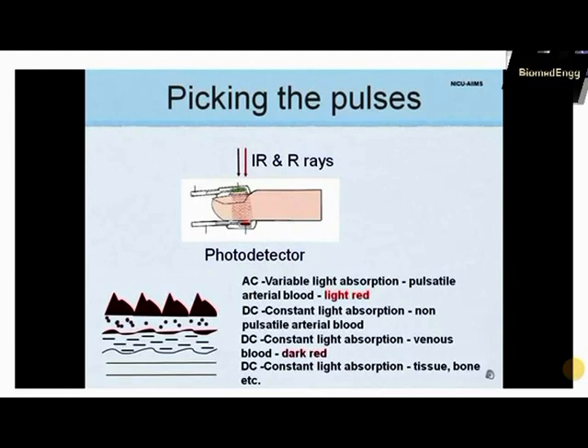Each pulse oximeter probe contains two light emitting diodes which emit red and near infrared wavelengths through a cutaneous vascular bed. A photo detector on the other side measures the intensity of transmitted light at each wavelength, from which the oxygen saturation is derived. This is based on data stored in the memory of the oximeter.